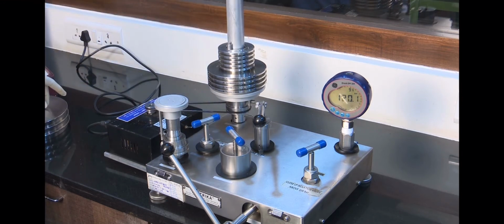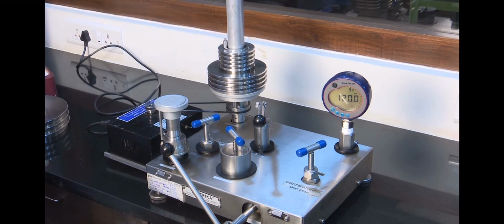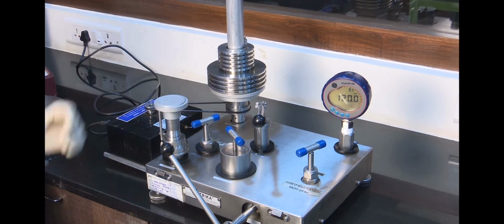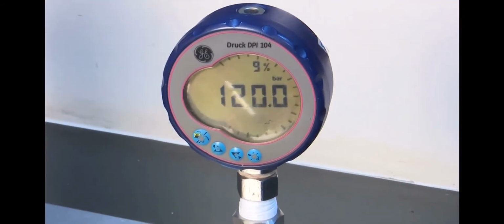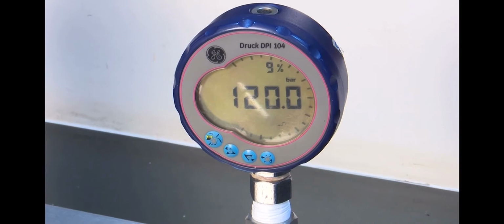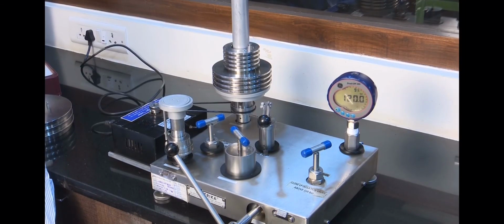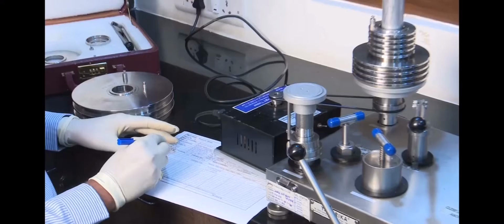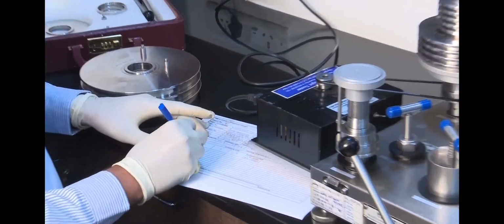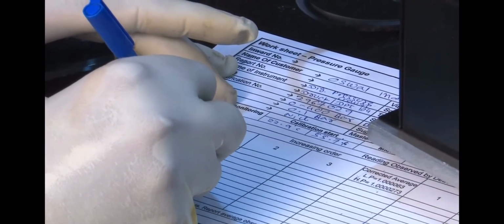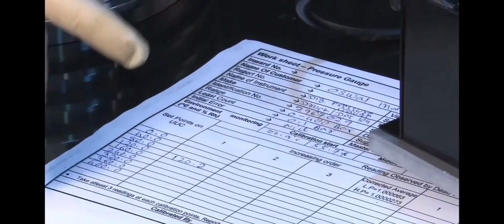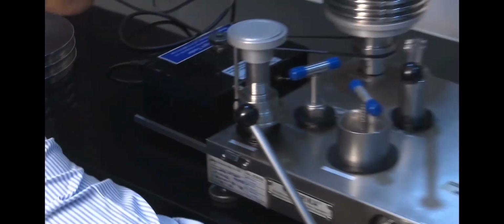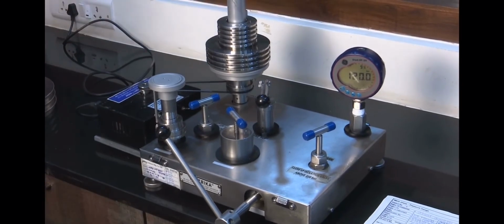Rotate handle clockwise and develop pressure inside the UUC. Now adjust the weight so that UUC shows 120 bar. Allow it to stabilize for 30 seconds. In the worksheet, record the value of weight adjusted on the dead weight tester against UUC reading. In the same way, we can perform calibration for all calibration points as per calibration method.